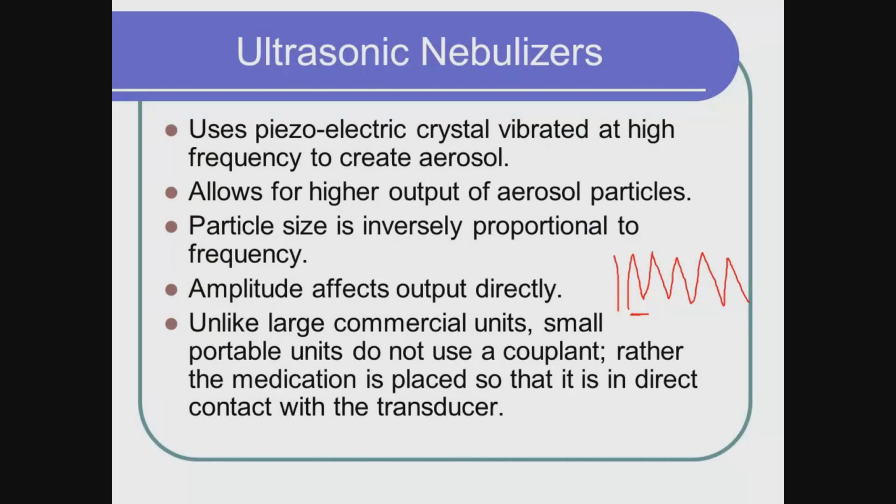Next group are ultrasonic nebulizers. You don't see these in itself that much anymore, but they basically used what's called a piezoelectric crystal, and this crystal vibrates when electricity is applied to it. That vibration allows for the medication to be nebulized. So it's not the typical way we use with a jet nebulizer where it draws up the medication. This is a totally different principle, but the nebulization occurs secondary to the vibrations.